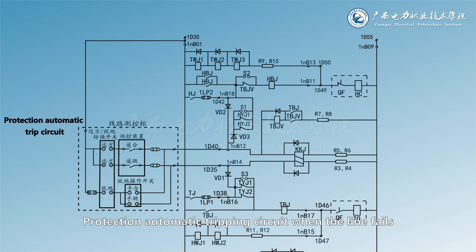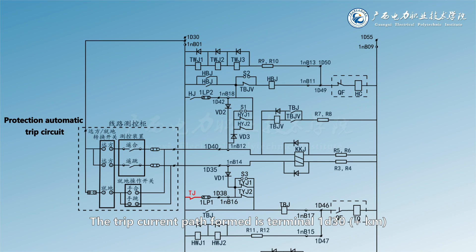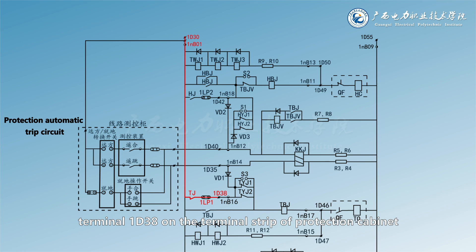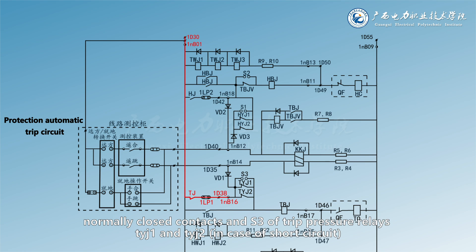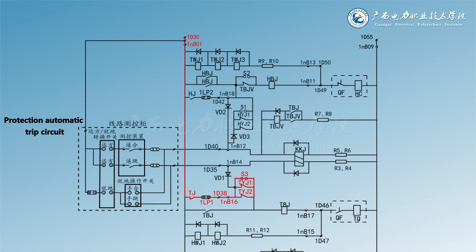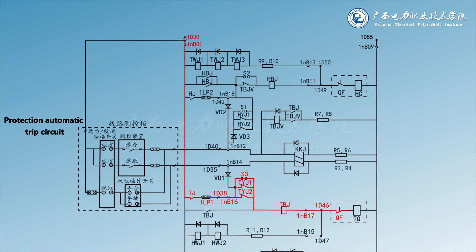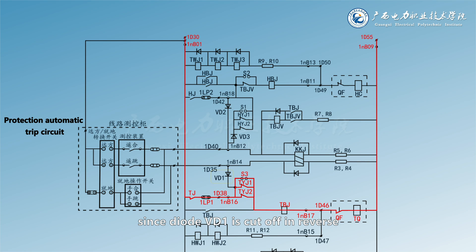For protection automatic tripping: when the line fails, the protection device will act, and the normally open contact of its tripping outlet relay TJ closes to trip the circuit breaker. The trip current path formed is: 1D30, 1NB01, 1LP1, 1D38, 1NB16, S3, TYJ1 and TYJ2, TBJ, 1NB17, 1D46, QF, TQ, 1NB09, 1NB15, 1D47. Different from manual tripping, since diode VD1 is cut off in reverse, the closed position relay KKJ will not return during protection tripping.